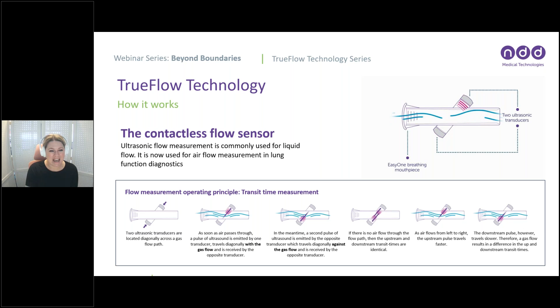So what are the operational benefits of that technical slide we just shared? We're using this to measure airflow for lung function diagnostics. This allows us to be manual calibration free. The ultrasonic flow measurement is highly accurate in all flow ranges, independent of gas composition, environmental pressure, temperature, and humidity. All of these things create a sensor that does not need to be manually calibrated during its lifetime.